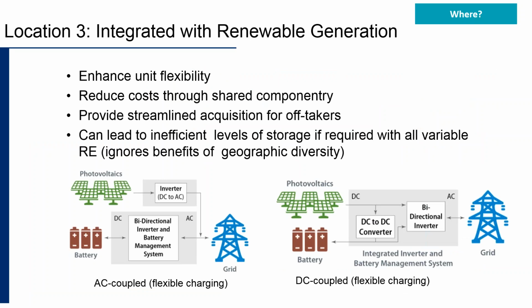The third application or location is integrated with renewable generation. Where we're seeing this most is integrating solar PV with energy storage, and there are different ways to integrate these technologies. Early deployments of storage with solar have had the storage co-located but not really integrated—called AC coupling, putting the inverter and battery on the AC side of the PV inverter. It's kind of a standalone application: they may share common engineering, siting, and a common point of connection to the grid, but they're not truly integrated. A potentially more cost-effective way is to actually couple the storage on the DC side of the inverter.